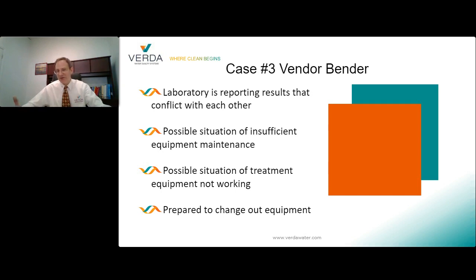So this potentially is a major issue. Wow, we've got to treat all the water, all the utility water. But one red flag made me question this new trend for our customer. When the water hardness got to 350, the hardness after the softener feeding the RO system was reading 180. So the customer either had an out-of-control water hardness issue and a malfunctioning water softener, or these results just weren't correct. So a call to this laboratory manager returned a response: calculations were checked, the readings were accurate. Here's the story again, the same thing.